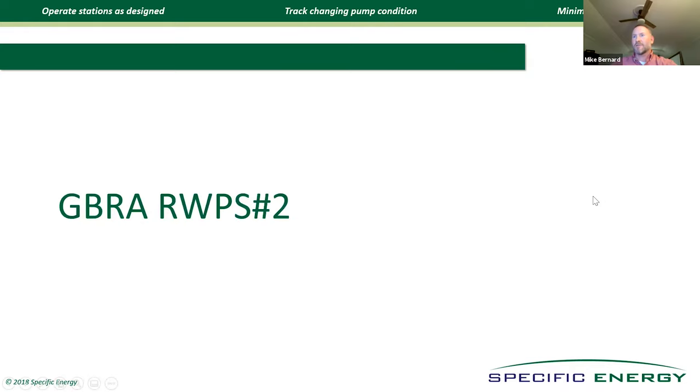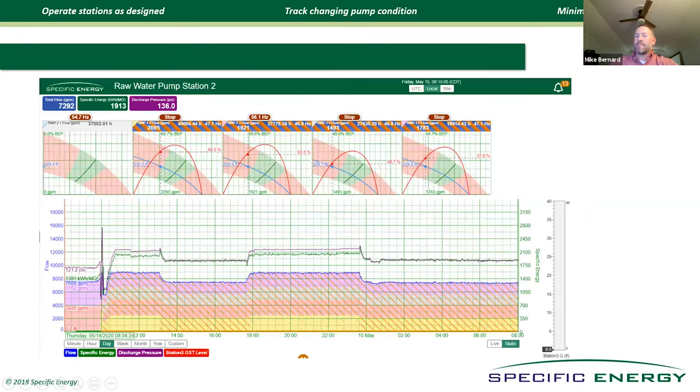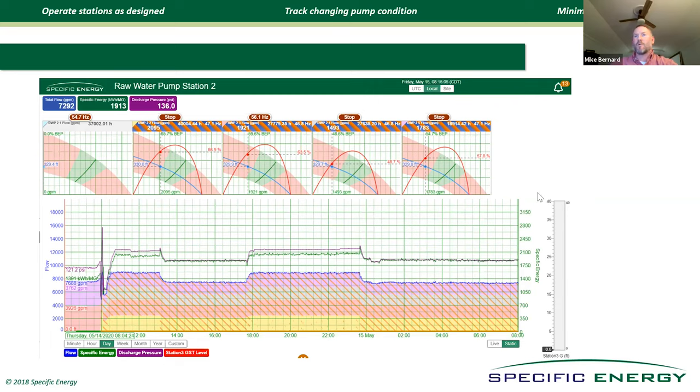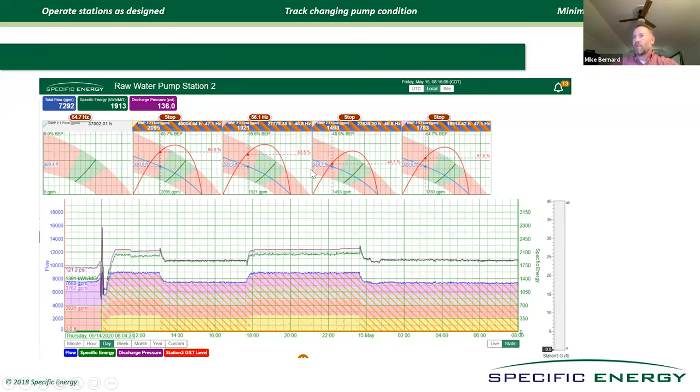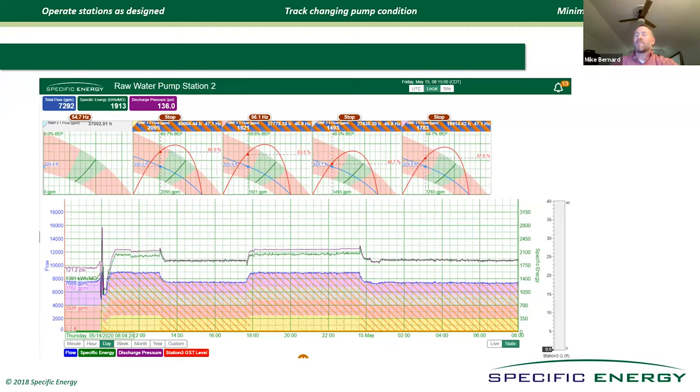I want to give a case study. Here's another utility in Texas that I'm sure most of you know, GBRA Guadalupe Blanco. This is their raw water pump station number two. When I first came aboard, I've only been on with Specific Energy since May 1st of last year, but when I came aboard, I would go into our dashboard every day and I would check to see who was doing well and who was not doing so well. When pumps are operated outside of POR, this crosshatch pattern comes up and you can see that four of their five pumps were running and they're all running to the left of POR and consuming a lot of energy. So I called Perry one day, our president, CEO and founder, and said, what's the deal? Why aren't they taking any of our advice?